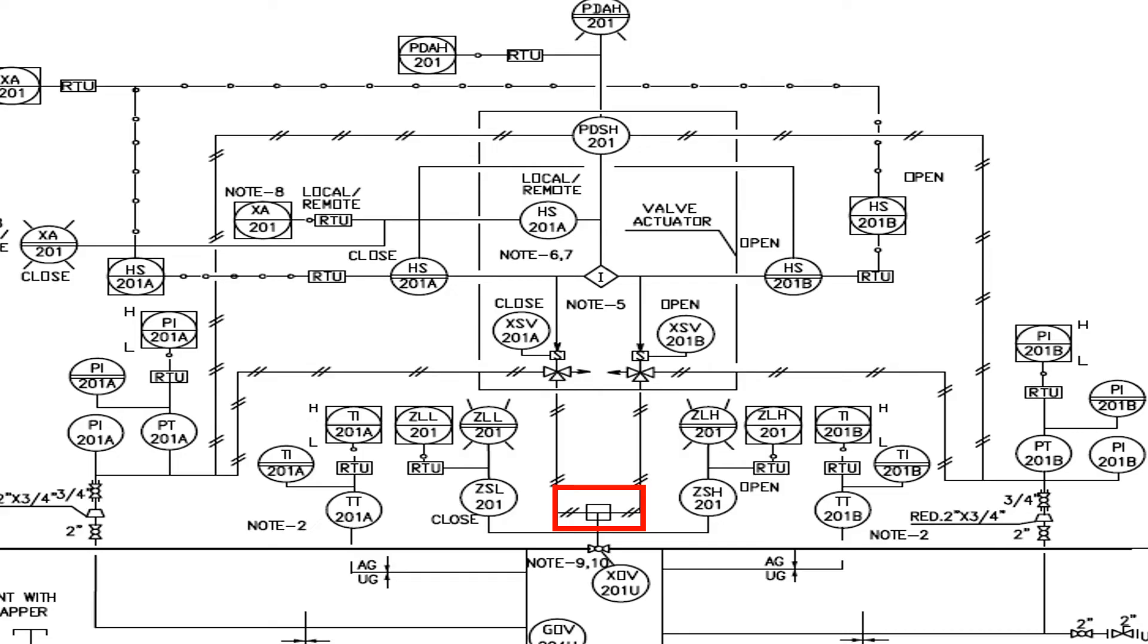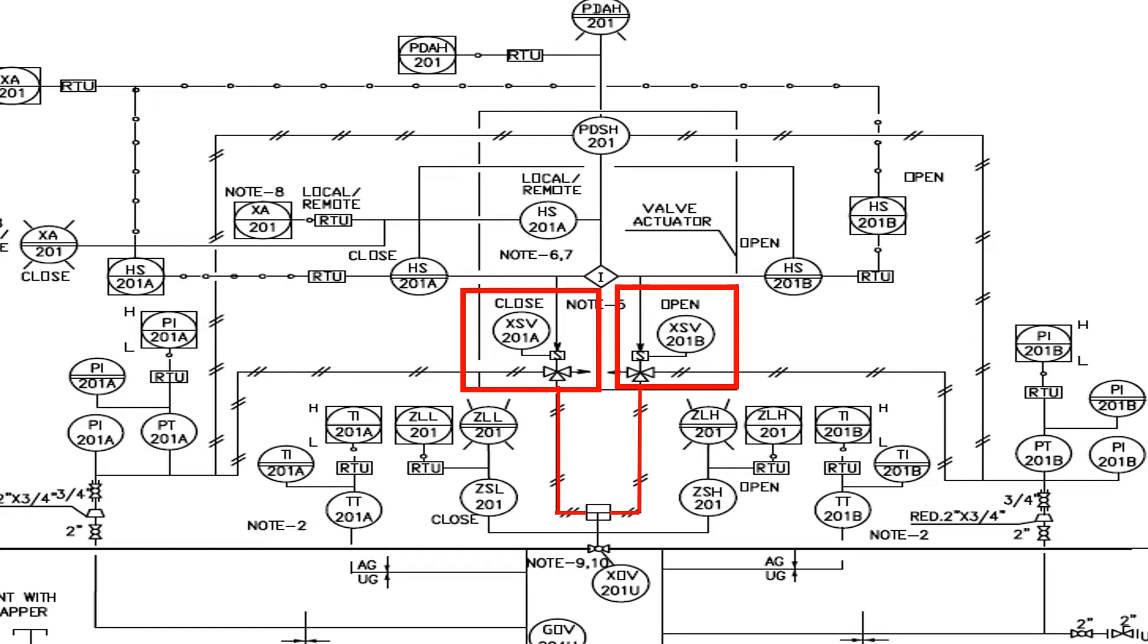ZLL and ZLH shows the corresponding running lights in local panel and control room. Now when we see the actuator of the valve XOV, we can understand that the valve is a pneumatic valve as pneumatic lines are entering the valve.